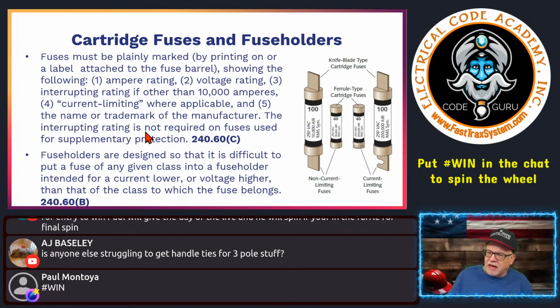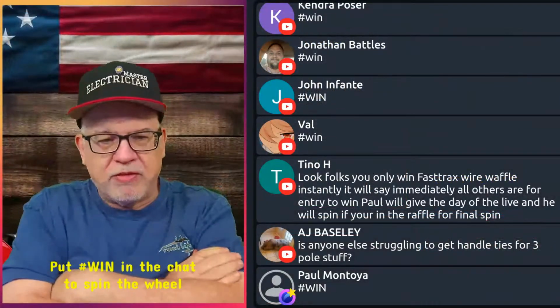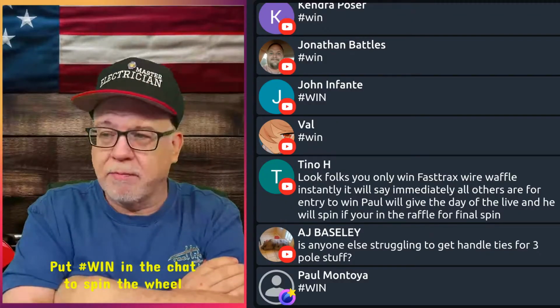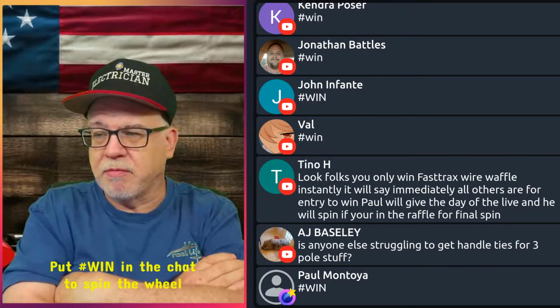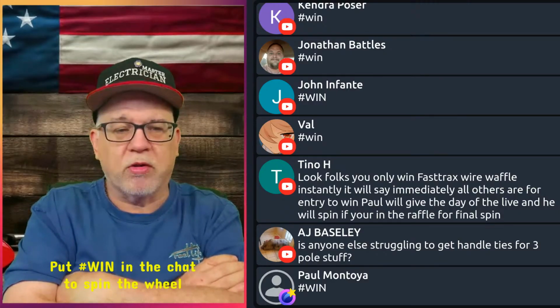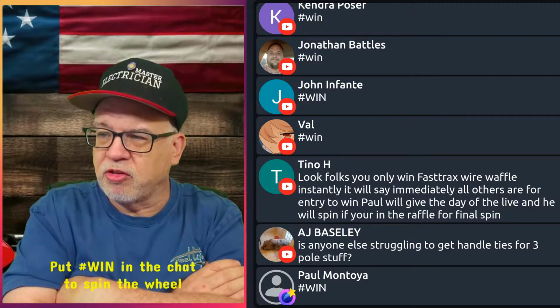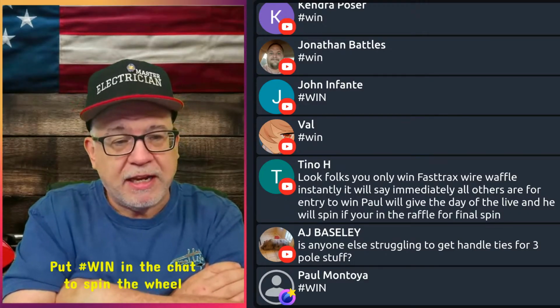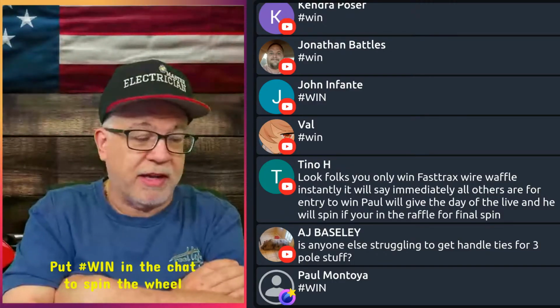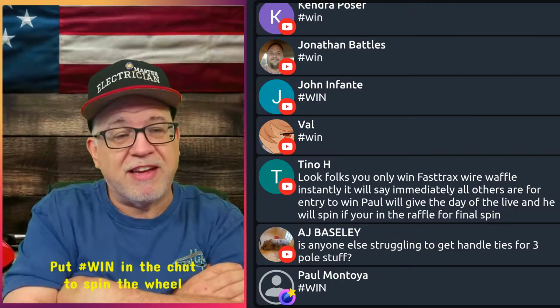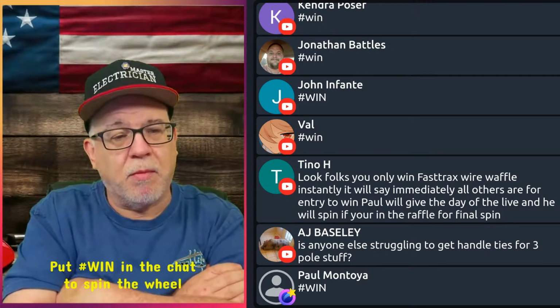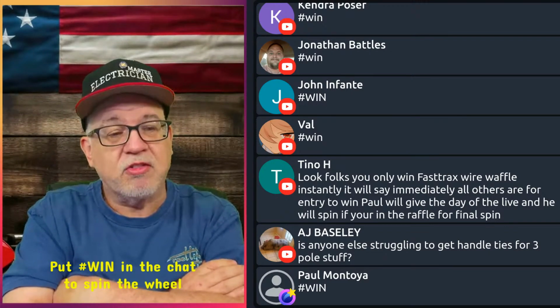The interruptive rating is not required on fuses used for supplementary protection. So if it's integral to a piece of equipment, it's not the main protection, it's supplemental. Although I want to be honest with you, we are in the wire and cable business, we're not going to go out of our way to make special fuses for something and not put a rating on it. It's just one more step that we don't want to do. So it's probably going to choose standard, and it's probably going to have the interruptive rating already on it, even though it's probably being used as supplementary protection. But just know that it's not required to have that interruptive rating marking on a fuse if it's being used as supplementary protection.